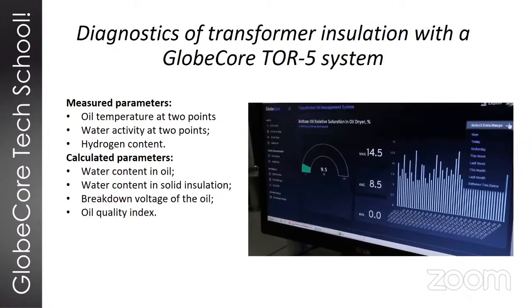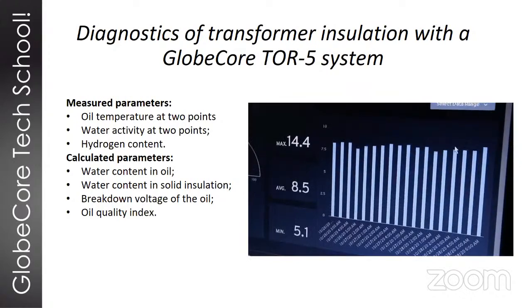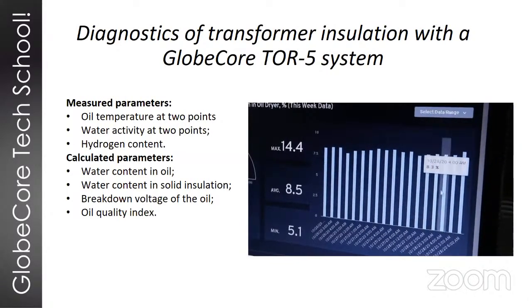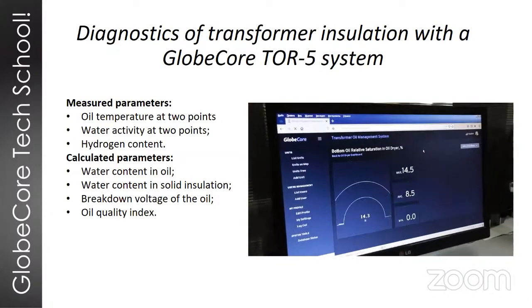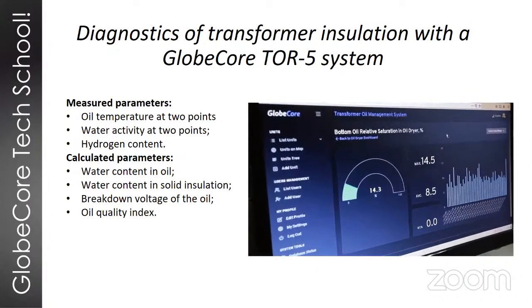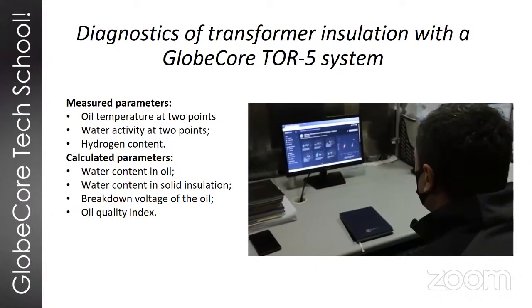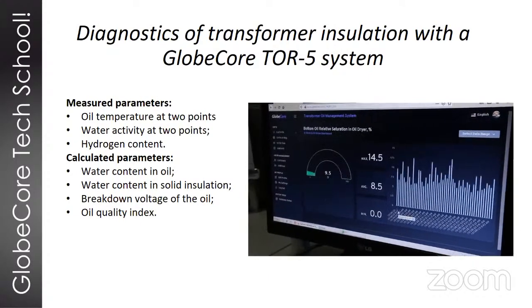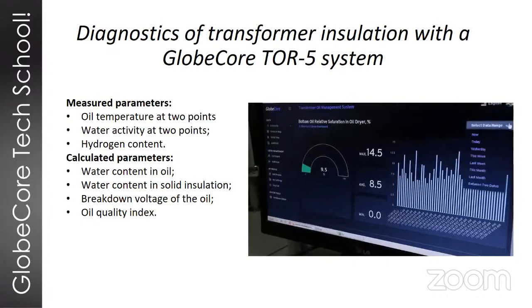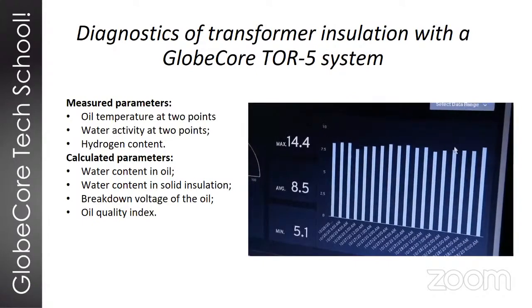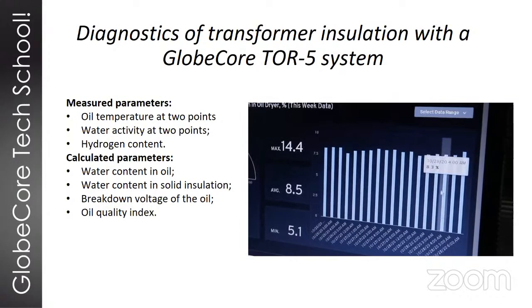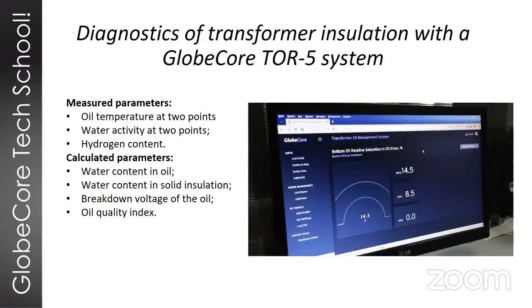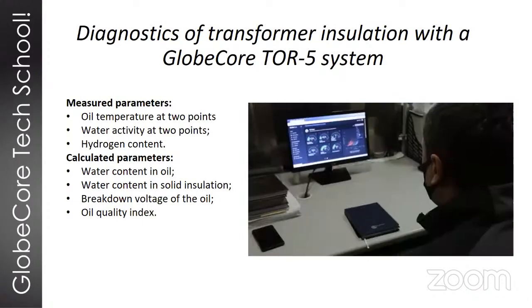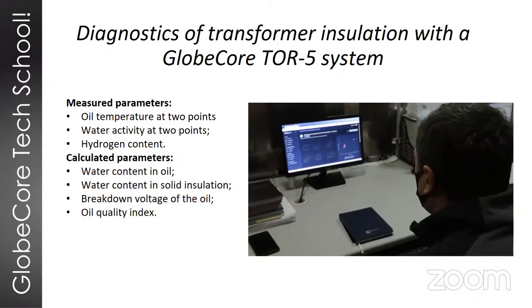So calculation of the oil quality index allows us to not measure those parameters, the acidity and the interfacial tension, and we will just know how old the oil is based on the oil quality index. Additionally, as an indicator of possible faults or problems with the transformer, we have a highly precise hydrogen sensor in the system. And as you may know, hydrogen is basically one of the first gases to form in the transformer in case of a problem.